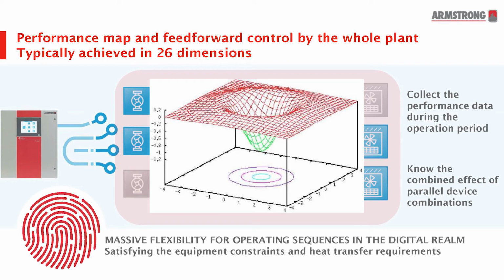And in most cases, we can still do 100% capacity flow even if one piece of equipment is degraded 20% in its performance. Then we expand the fingerprint wider and look at the whole chiller plant, so the whole cooling system can have its own fingerprint. What we do to optimize the plant is take the combination of all those equipment performance maps, real-time digital data, and combine the ones that add up to the required load and wet bulb temperature of that given operating condition the plant is experiencing at that time.